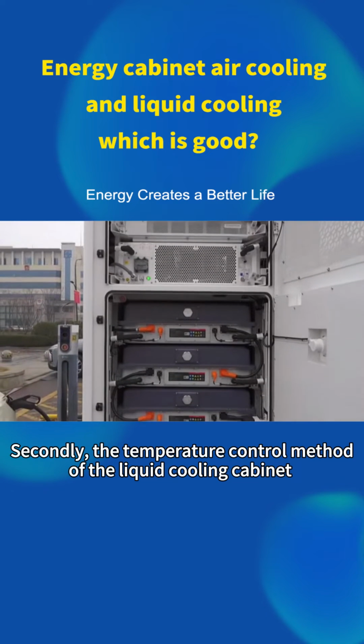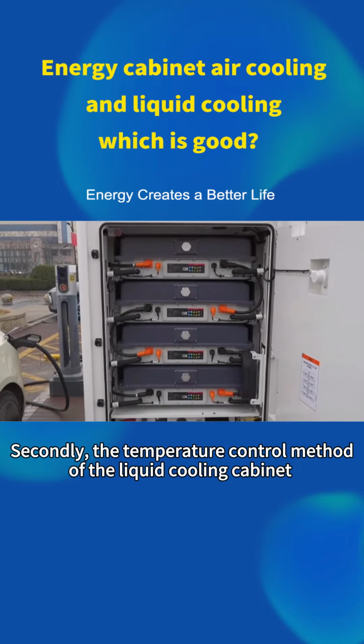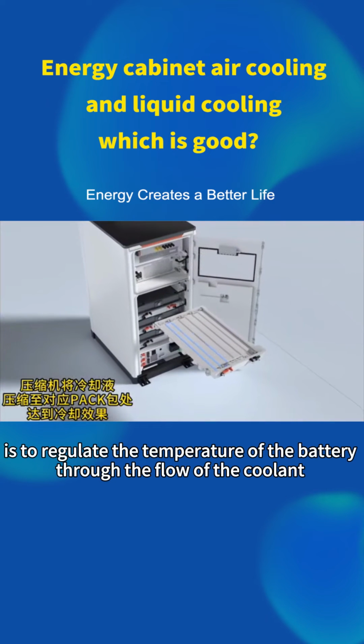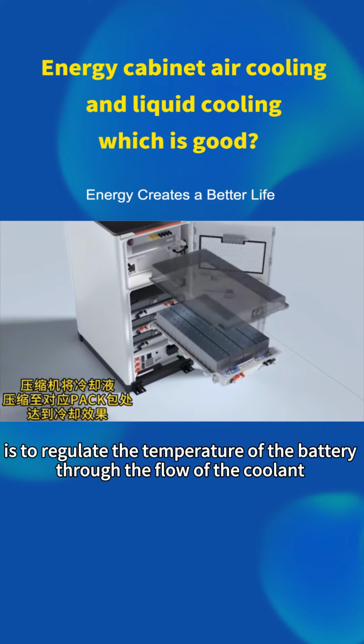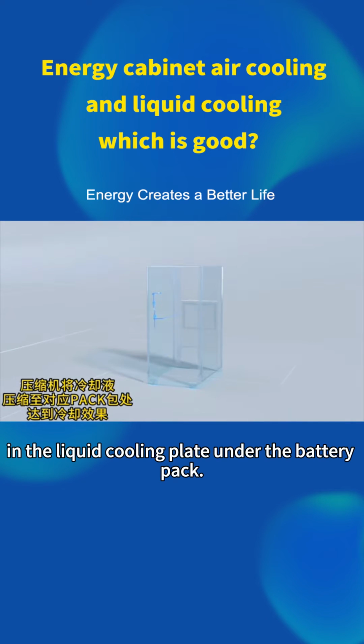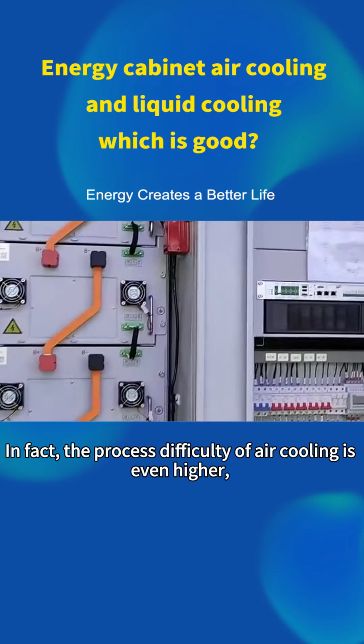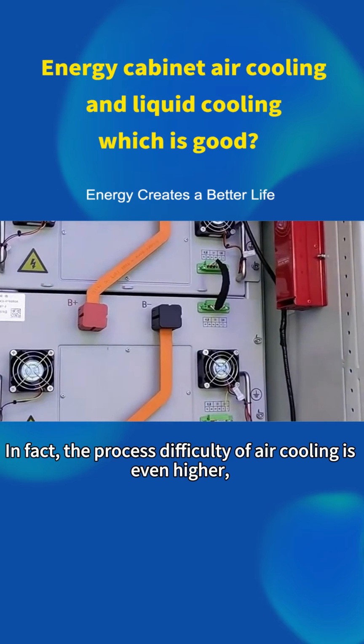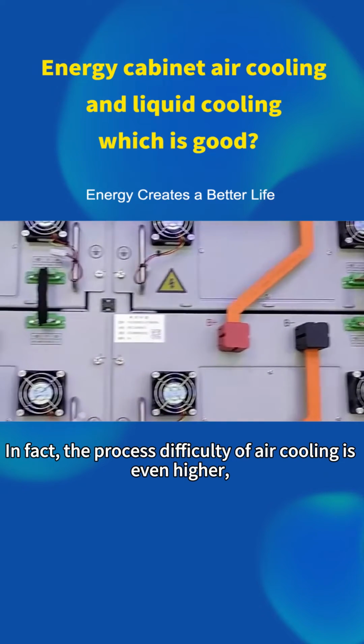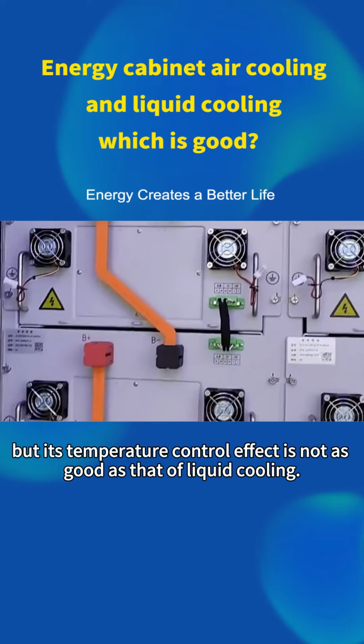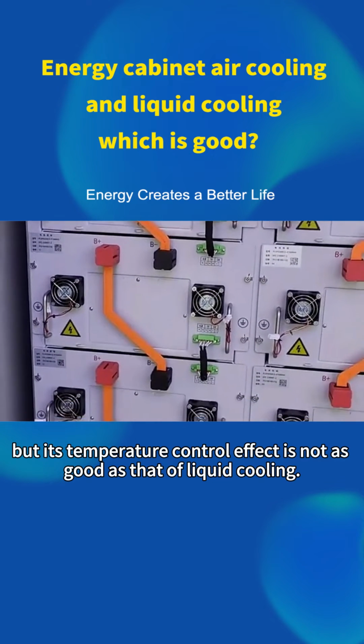Secondly, the temperature control method of the liquid cooling cabinet is to regulate the temperature of the battery through the flow of the coolant in the liquid cooling plate under the battery pack. In fact, the process difficulty of air cooling is even higher, but its temperature control effect is not as good as that of liquid cooling.